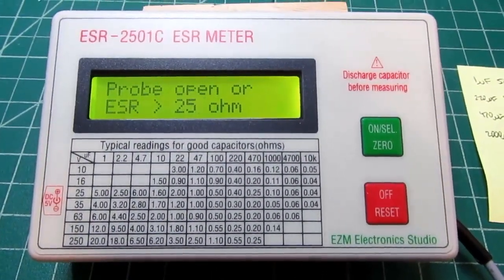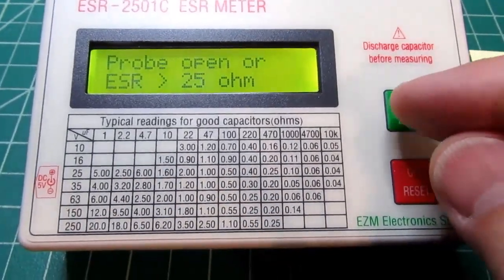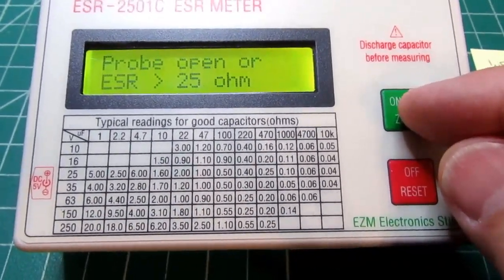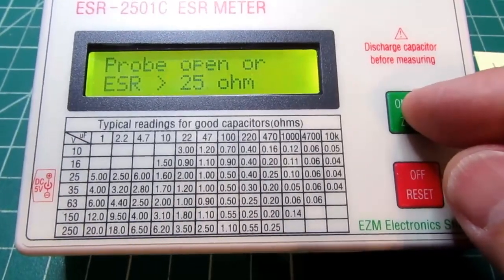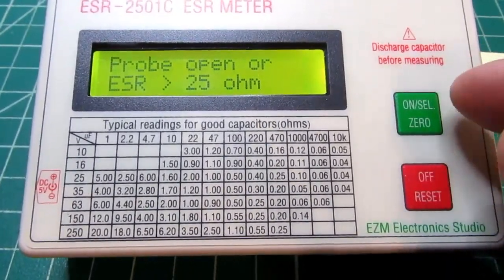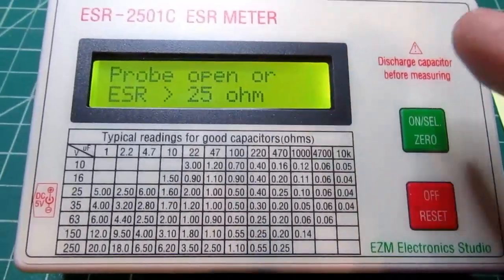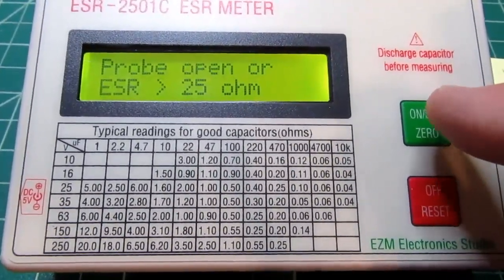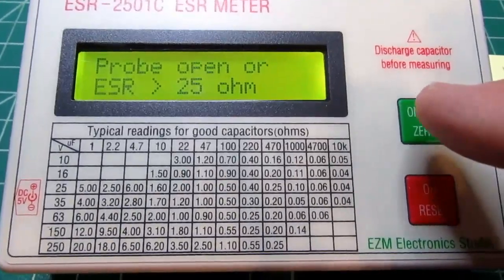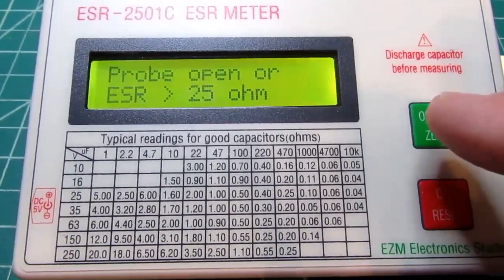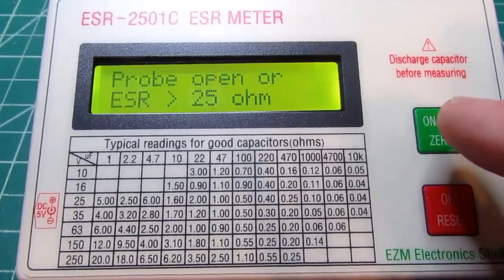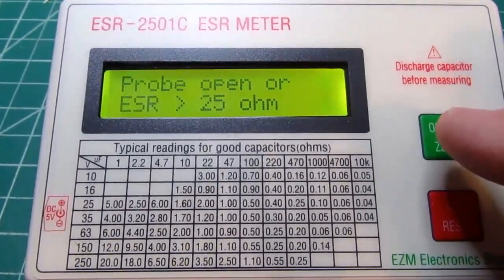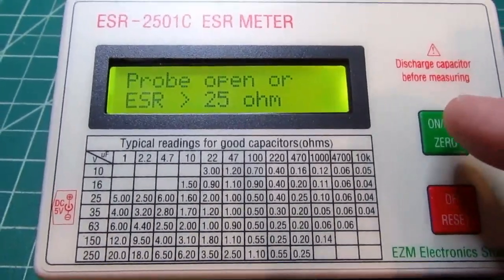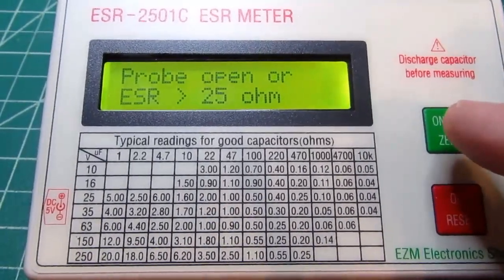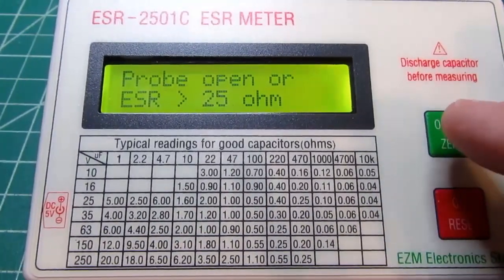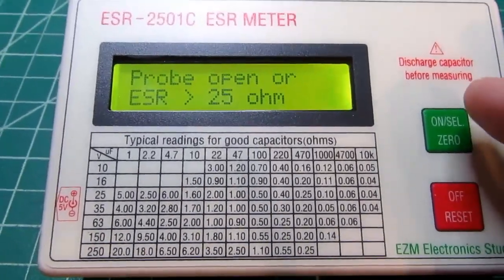Okay, what else do we have? So you can force this to do a new zeroing by pushing the green button, but when you do that, it generally changes the mode as well. I have found that sometimes I can get it to re-zero without changing the mode. There is no manual, but from the fragments of information I've found online, and my own empirical testing, I haven't found any rhyme or reason to when it changes mode or when it does not, if I'm just trying to get it to re-zero and stay in the same mode.